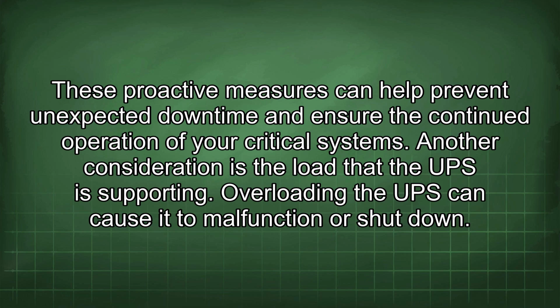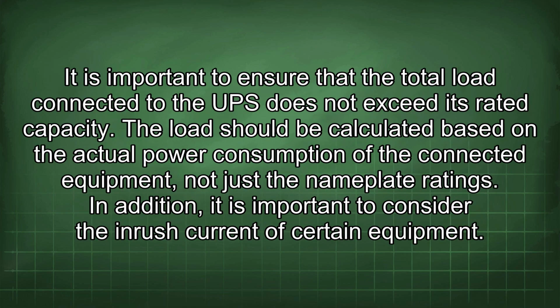Another consideration is the load that the UPS is supporting. Overloading the UPS can cause it to malfunction or shut down. It is important to ensure that the total load connected to the UPS does not exceed its rated capacity. The load should be calculated based on the actual power consumption of the connected equipment, not just the nameplate ratings.